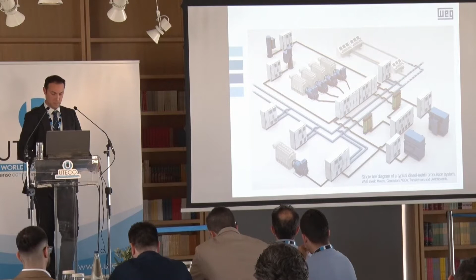When we do that, we also help the customer with a lot of engineering. For example, here the customer wanted a motor to start a jet pump on a dredger, and also the generator. So we calculated for him what the size of the generator should be to start up that motor with an auto transformer in the middle. We gave him all the parameters and calculations, and then he went to the auto transformer manufacturer with 'this is what I want.' That's how we cooperate in packages like this.